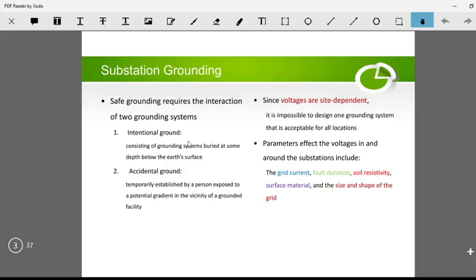There is another type called accidental grounding. This grounding happens temporarily, established by a person exposed to a potential gradient in the vicinity of the ground facility. For example, when working in the substation, if you touch something, a ground path could be created through your body. This is called accidental grounding.